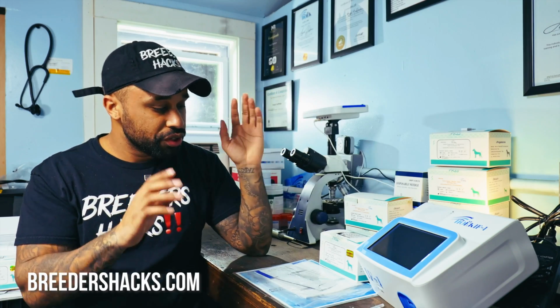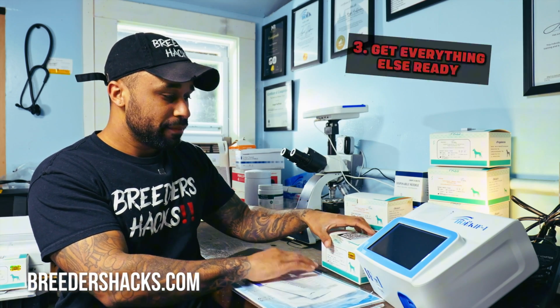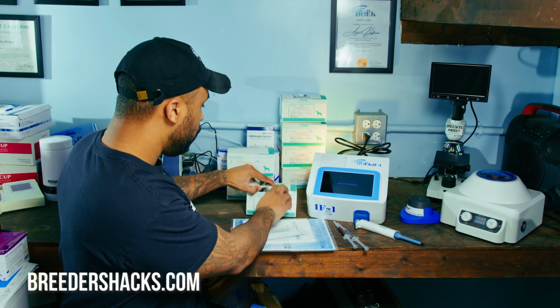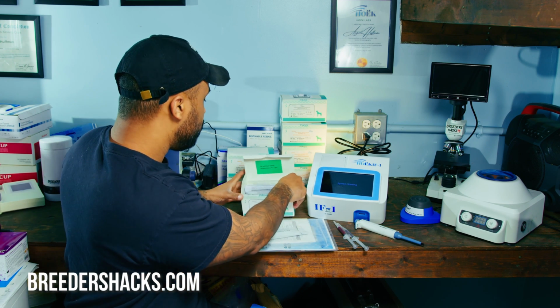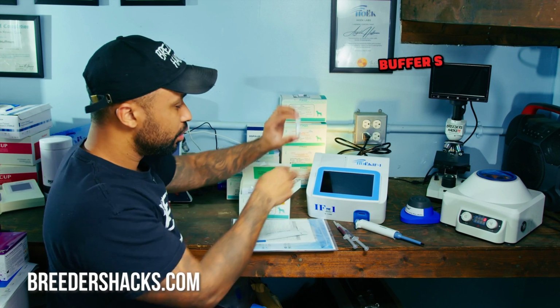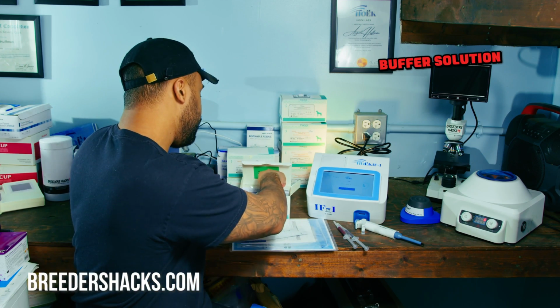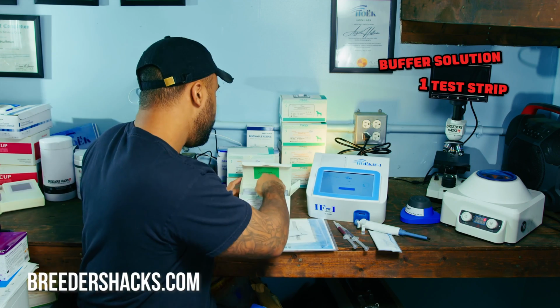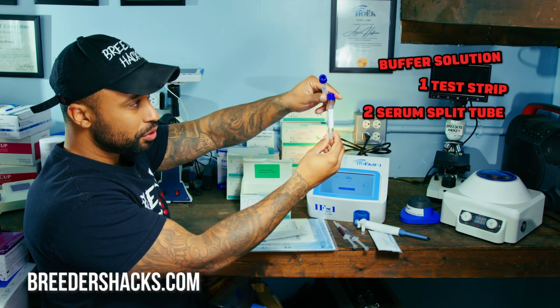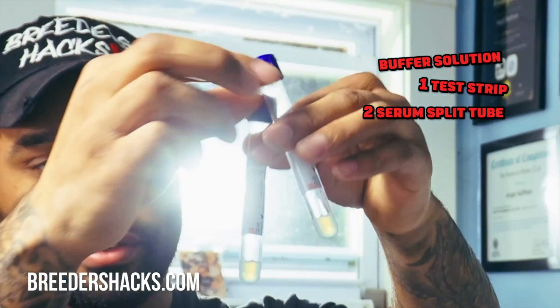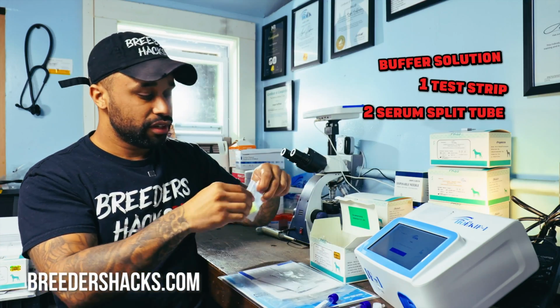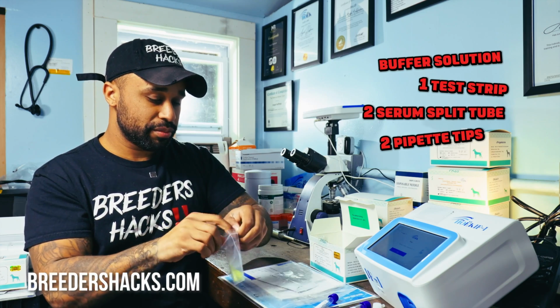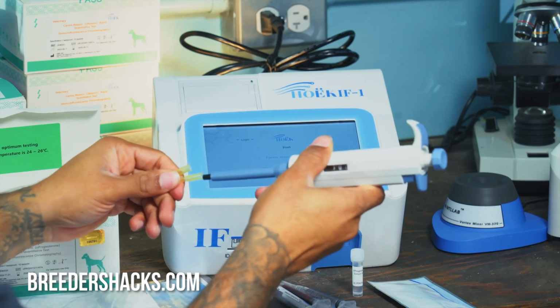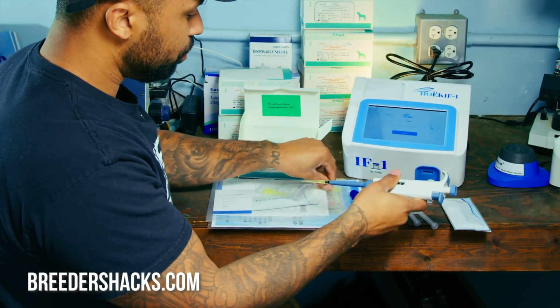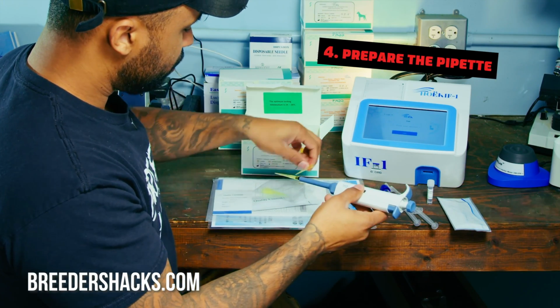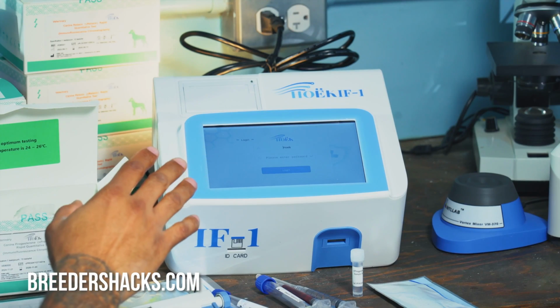In the meantime, what you can do is get everything else ready. As the machine is turning on, you want to open up your box of test strips. For one test, you'll take out a buffer solution, one test strip, and a serum split tube. You may need two of them, and you'll see why in a minute. So you'll need these two tubes, and then you'll want to take out like two pipette tips. You want to have these things ready to start running your test. So I'll take one of the pipette tips and just have it ready on our pipetter. Our machine is powered up.